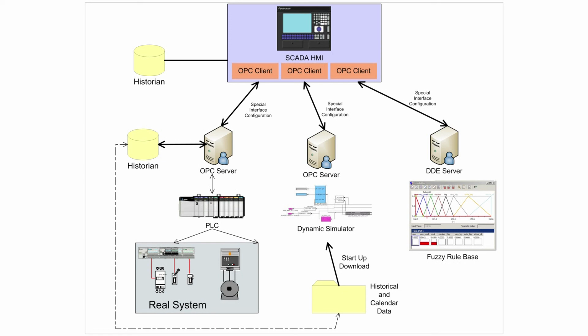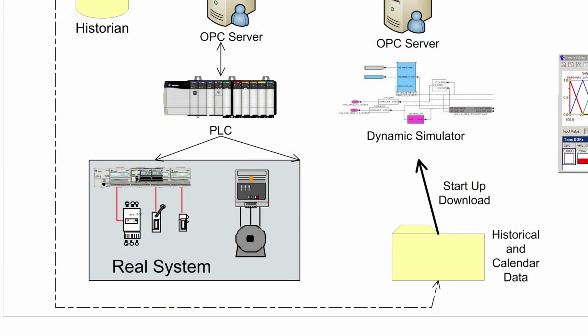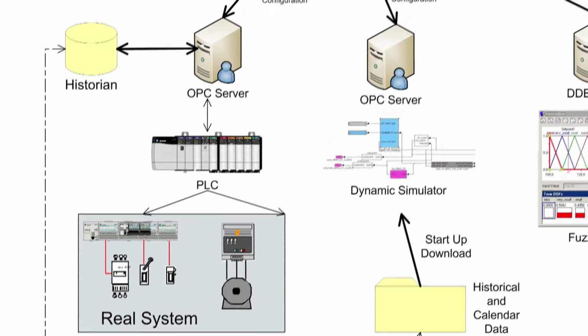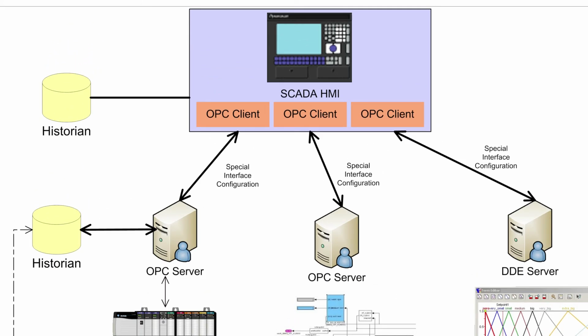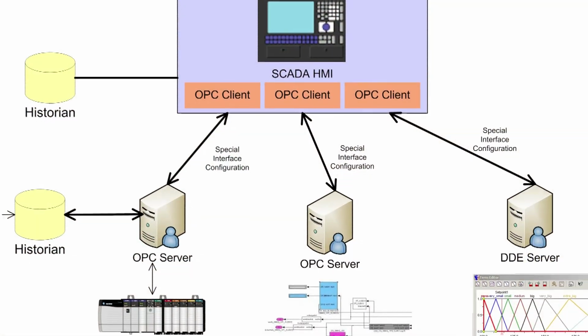That's, I think, what we see on this figure also illustrated. Here is the structure of the system. At the left down corner, there is a real system, it means the water distribution system, controlled by typical PLCs, the industrial computers. And via an OPC server, it's connected to the SCADA HMI, which is the system with screens used by the operator to control the water distribution system. And our simulator runs in parallel with the real system, and it's connected also via the OPC server.